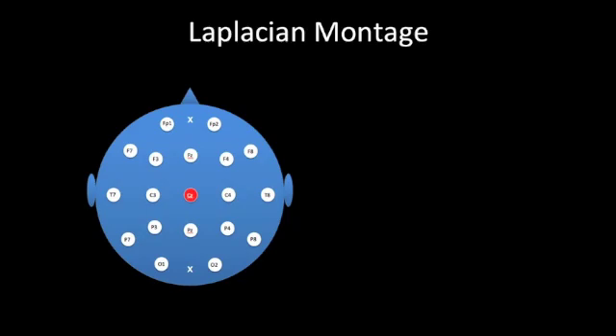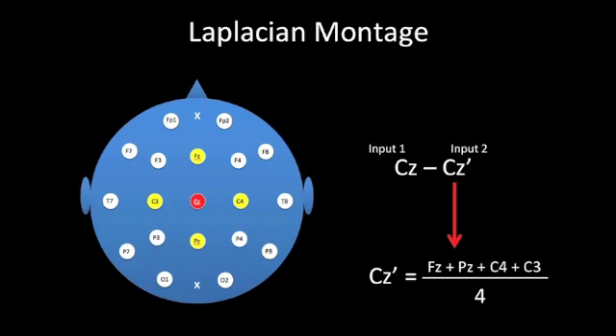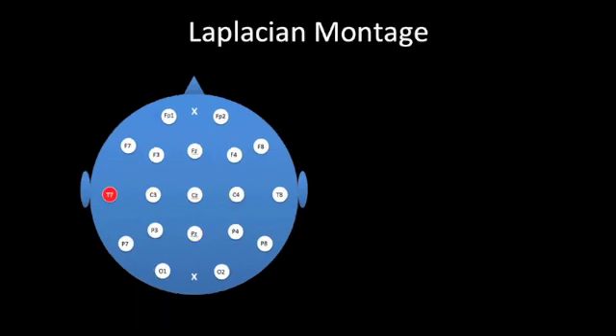One way to get around reference contamination is to use something called the Laplacian montage. The Laplacian montage is probably used least often among EEGers, mainly because it is very difficult to conceptualize. In general terms, we are always comparing one electrode position to an average of its nearest neighbors. For example, we would compare Cz to its four closest neighbors, expressing this as a first input Cz, and a second input Cz', which is an average of the four adjacent neighbors. Special consideration has to be given to electrode positions on the edge of the head where there are fewer adjacent neighbors.